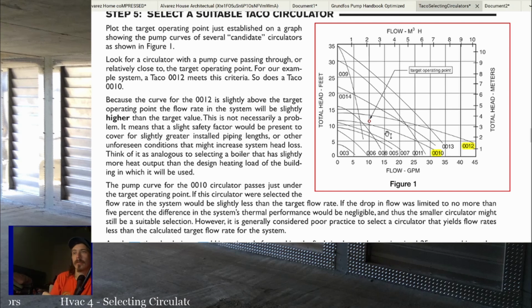Generally, within reason, having a little bit of extra head loss, if they added 5 more 90s in there than you designed for, or you're not sure how many 90s there are in there if you're reverse engineering the system and you're trying to make sure that whatever pump you put in is going to have a little bit of wiggle room, then you want to make sure you pick something that's slightly higher. And it just says right here, it's not necessarily a problem. It means you got a slight safety factor to cover slightly greater installed pipe lengths or other unforeseen conditions that might increase system head loss.